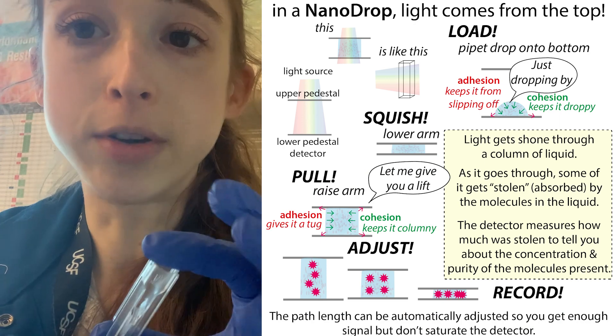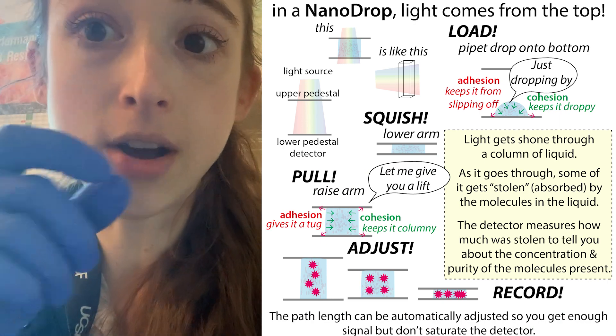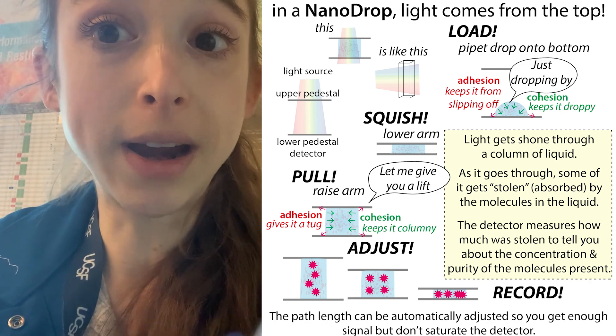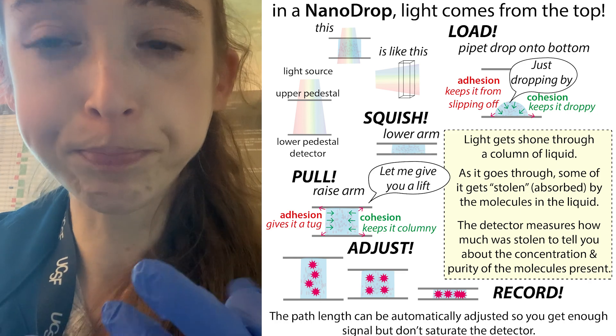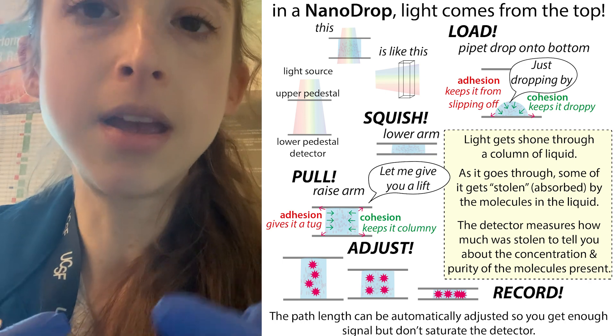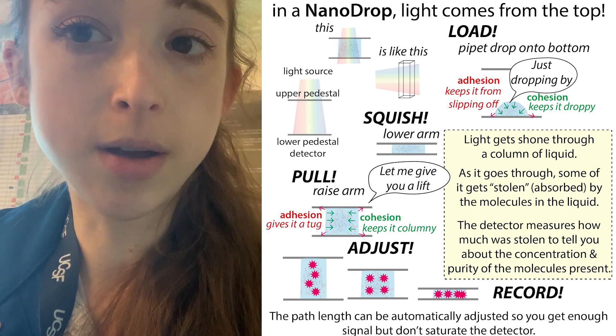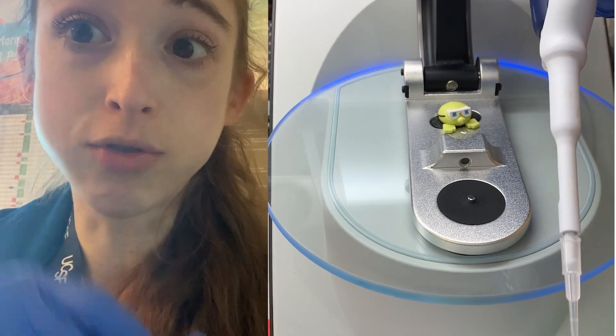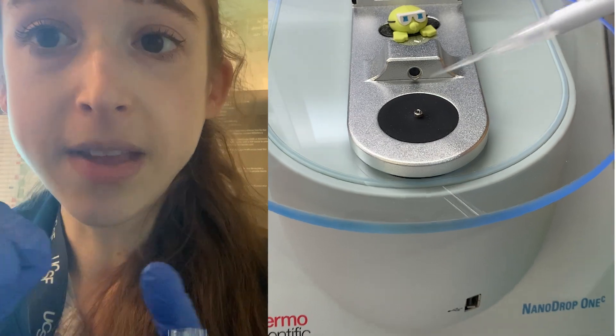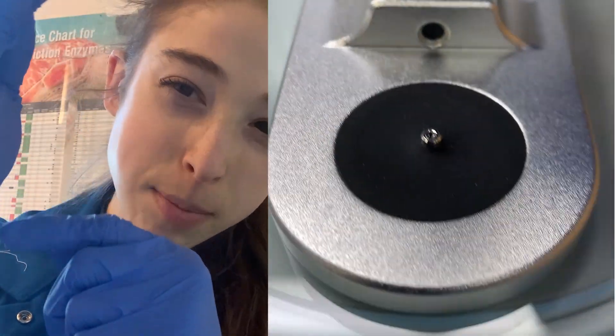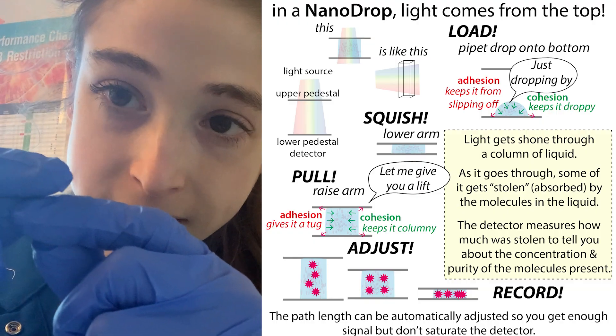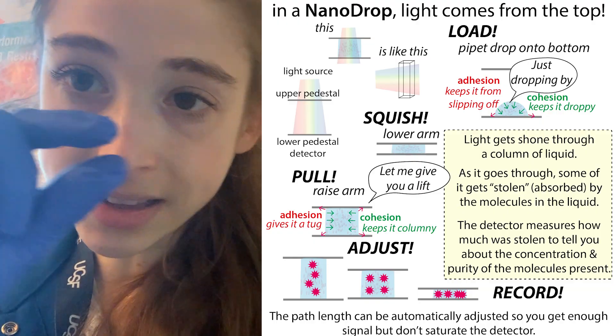In a nanodrop, however, it actually changes its column length automatically to adjust for the concentration of your sample. So you can take a wide range of samples and you don't have to dilute them - it's really awesome. But where is the column in a nanodrop? How it works is you place a small drop of liquid containing your molecules of interest onto the pedestal, then you bring the top metal part down, and it pulls up a little to make a small column of liquid.